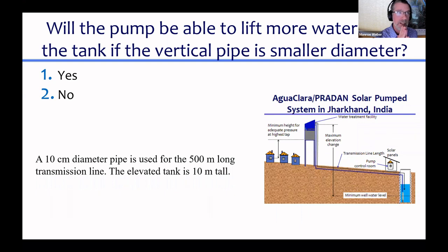Like I take that diameter and I drive it to 0. At some point, that pump's not going to be able to pump any water through that pipe. So what is the pump actually experiencing? There's this common misunderstanding that the big pipe of water somehow makes the pump struggle, but it doesn't.